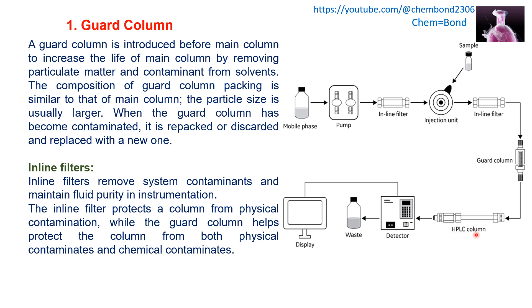To increase the lifetime of the main HPLC column, a guard column is introduced before it to intercept any particulate material coming from the mobile phase, thereby protecting the main column. A guard column removes particulate matter and contaminants from solvents. The packing material composition of the guard column is similar to that of the main column, but the particle size in the guard column is larger. When the guard column becomes contaminated, it is repacked or discarded and replaced with a new one.